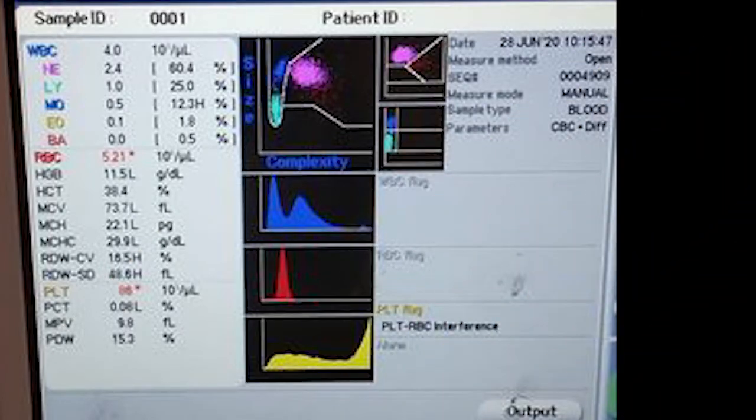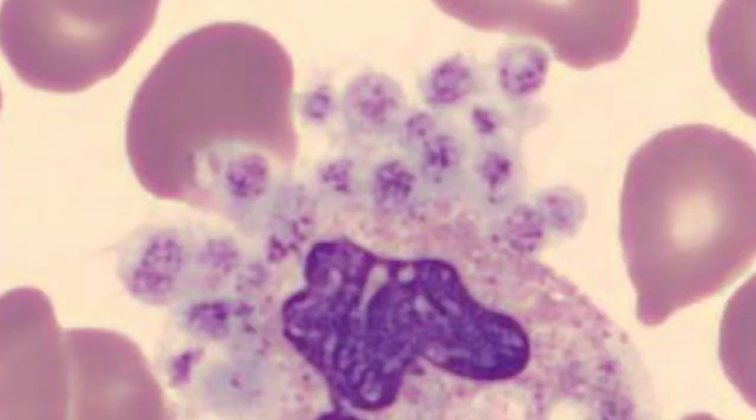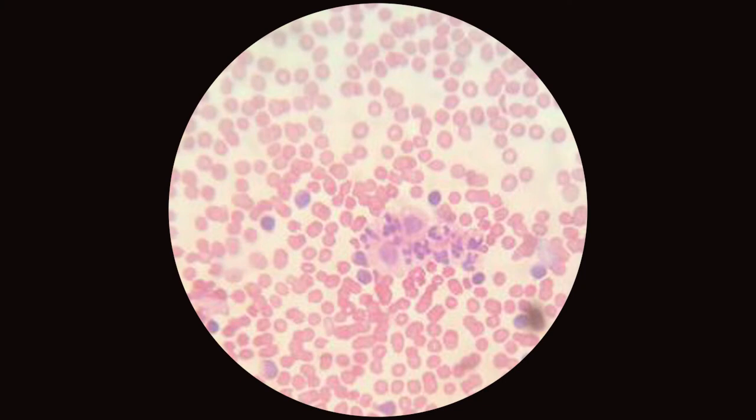Low WBC count. If a sample has a microclot with leukocytes trapped in it, it can give a low WBC count. Leukocyte clumps also cause a low count, as a WBC clump is counted as 1 WBC in the instrument. High WBC count. Microclots or platelet clumps are counted as WBCs in the instrument and can cause a false high WBC count. Please check the peripheral smear for platelet clumps, which are often located in the periphery of the smear.